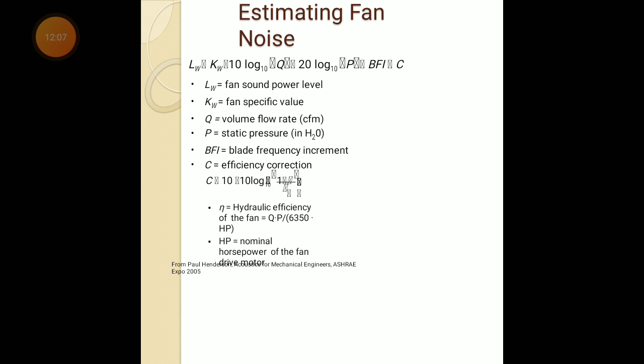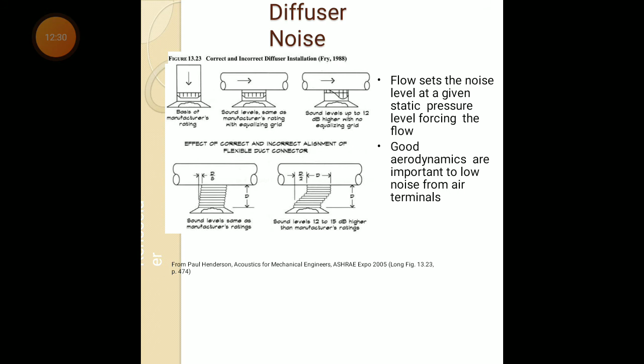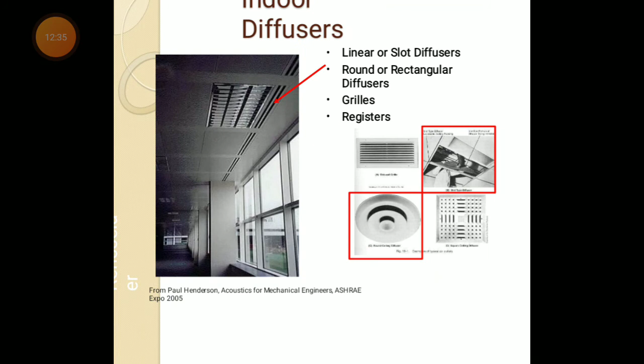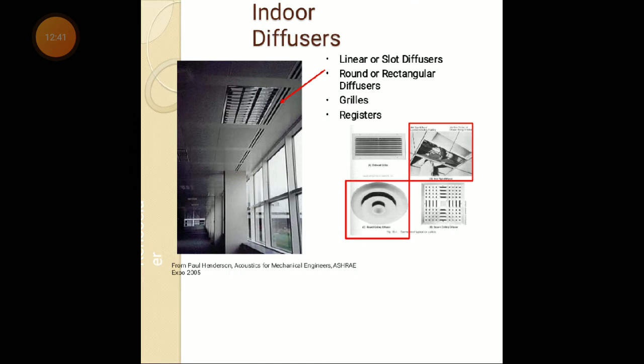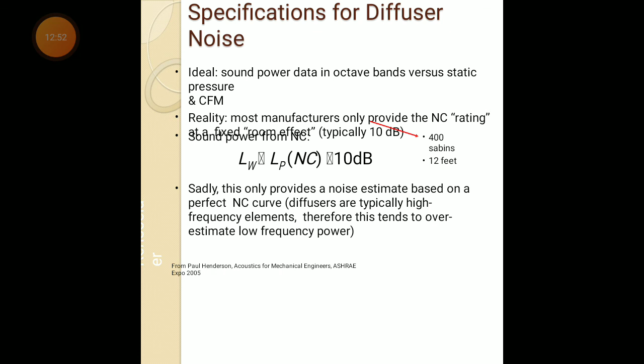So diffuser noise. Flow sets the noise level at a given static pressure forcing the flow. Good aerodynamics are important to low noise from air terminals. So these are the diffusers which are fitted. Some diffusers are also shown here. So diffuser noise can be calculated by this formula: LW is equal to LP of NC plus 10 dB.